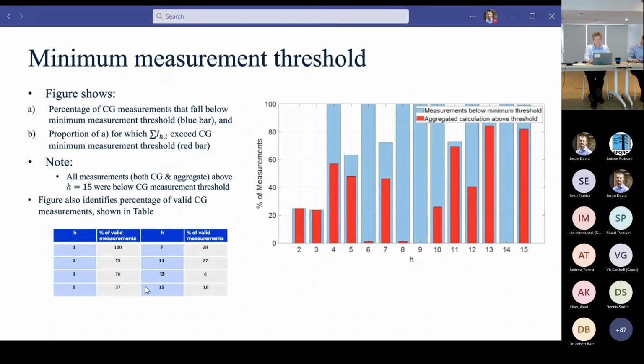So, the number of measurements that are actually valid through the collector cable across each harmonic order. For the first, obviously, it's going to be 100%. But for the second, we've only got 75% of measurements that are valid. For the third, that goes to 76%. But then as we go up in frequency, it falls off drastically. For the fifth order, only 37% of overall measurements are valid through the collector cable, and it goes down as the frequency goes up. The reason we stop at the 15th is that above the 15th, we have no valid measurements for any harmonic orders through the cable, so those measurements were completely disregarded.